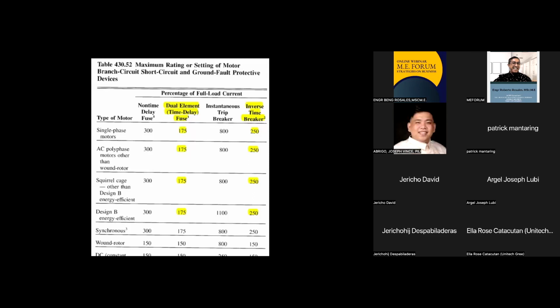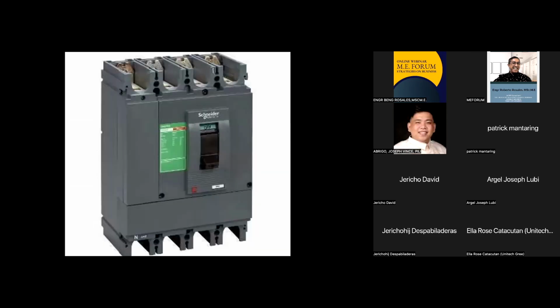In an electrical system, always remember, the ampacity of your wire should be higher than your breaker. Why? If your breaker is higher than the ampacity of your wire, the tendency is that the wire burns before the breaker trips. So you need to be cautious when designing wire ampacities, because your wire might already be burning and the breaker has not tripped. Then what is the use of your protection device? Okay?